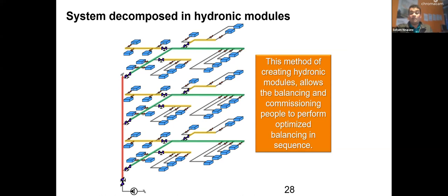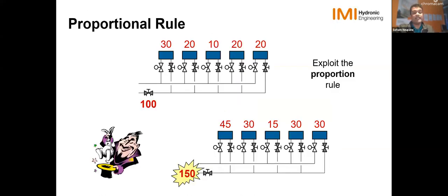Earlier, if you remember, I said we want partner valves to make balancing easier, and that is by exploiting the proportional rule. So what's the proportional rule for balancing? When we have a partner valve, like the one we looked at earlier, let's say we have 100 GPM here, and 30, 20, 10, 20, 20 GPM going in there. The proportional rule says that whatever changes we make on this valve, the flow downstream is going to change in the exact same proportion. Say we now have 150 GPM going in here. You saw a 50% increase in the flow on your partner valve, so you'll see the exact same 50% increase in the flow rate in each of the valves at your terminals as well.